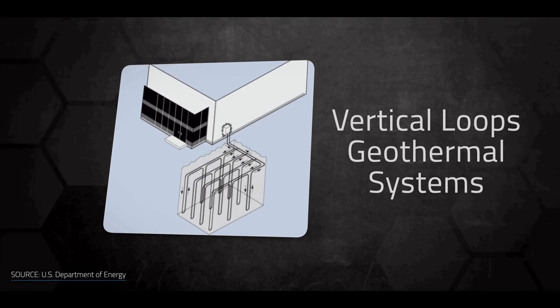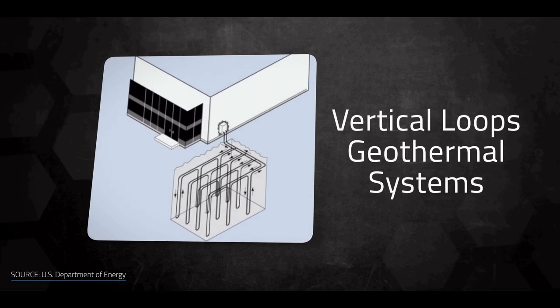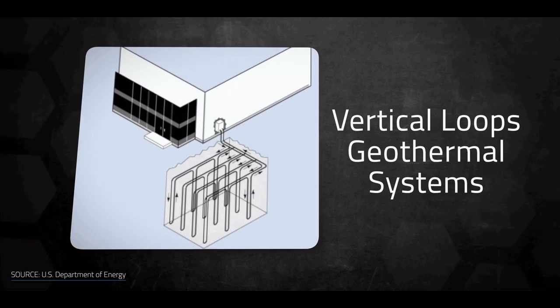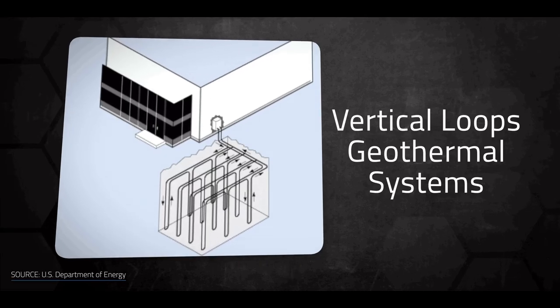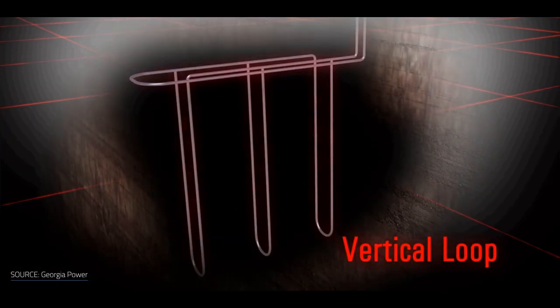in the ground. In vertical loops, as the name implies, they're vertically oriented, and they require several holes to be drilled straight into the ground. The number of holes, their depth, the spacing between them, and the volume of fluid that's in the tubes depends on the soil, temperature variations, and the house's heating and cooling needs. A great advantage of vertical systems is that they can be installed within a very small area.